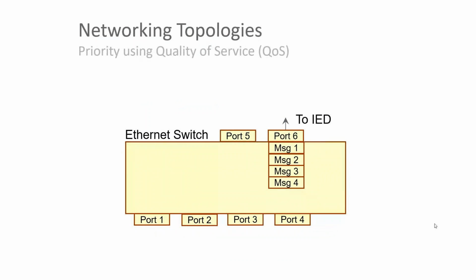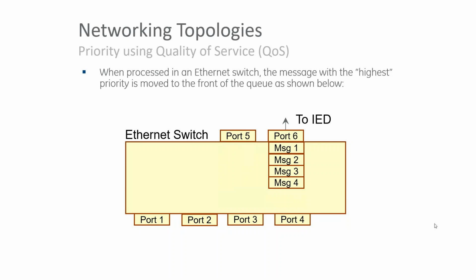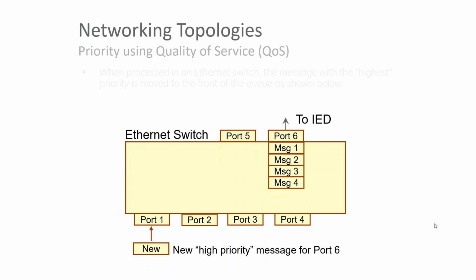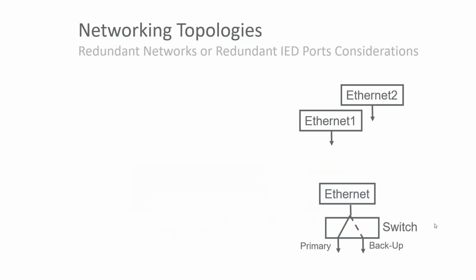Within the Ethernet protocol, there is a quality of service. Each piece of data in the Ethernet network might be more important than other pieces of information, so you can create priorities for those messages. What happens in a switch when a message comes in? If multiple messages come in to go on the same port, the switch creates a queue of those messages, and the first one that came in is the first one that goes out, and so on. But if a message comes in that has a higher priority than the previous messages, it will bypass the queue, go to the top of the queue, and get where it needs to go. So data that have higher priority will have higher priority within the switch to get where they need to get to. One example of that is GOOSE messaging for tripping purposes, and we'll talk very briefly in a couple of minutes on that.